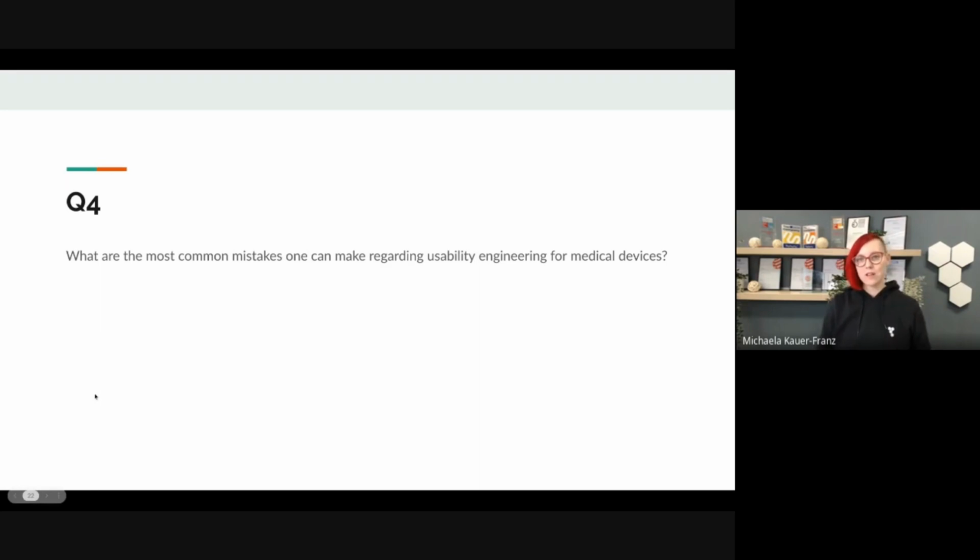For the FDA, it's totally different. They are very aware of the topic. And the rejections that we get from there are almost every time based on, okay, you have conducted a usability study, but you applied the wrong method. You chose the wrong user group, you have the wrong setting, you have the wrong test dummy, you have the wrong cases, you didn't document your risk properly. So you need to be a lot better if you want to go to the US market, if usability or human factors engineering is required. So that's from the formal side.